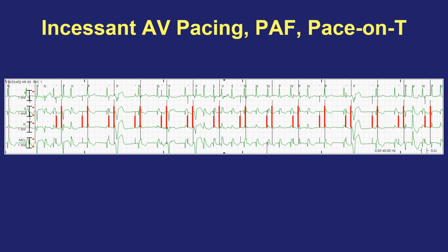And we reviewed before that you can easily tell a pacemaker to do this if you program it to a very insensitive mode, a very high sensitivity number, which means it's very insensitive, or if the mode is programmed to asynchronous, DOO, or the asynchronous button is pushed. And unfortunately, there are consequences to asynchronous pacing without sensing native activity, and there are two of them in this case. One is that sometimes the atrial pacer spike is occurring in a vulnerable time during atrial diastole, and it is causing repeated episodes of atrial fibrillation.